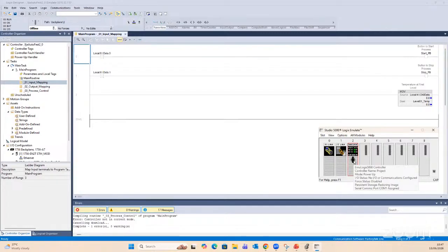But then you can still make some adjustments on the PLC. In run mode, you cannot make any program adjustment. You cannot make any adjustment whatsoever. You can't download into the PLC in run mode. But if you are doing online edits, you can put the PLC in REM mode. But if you want to download a fresh program, you have to put your PLC in program mode.